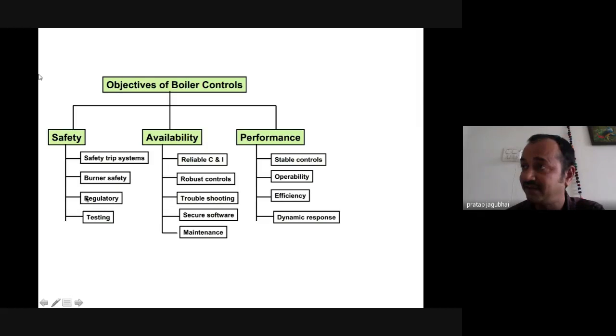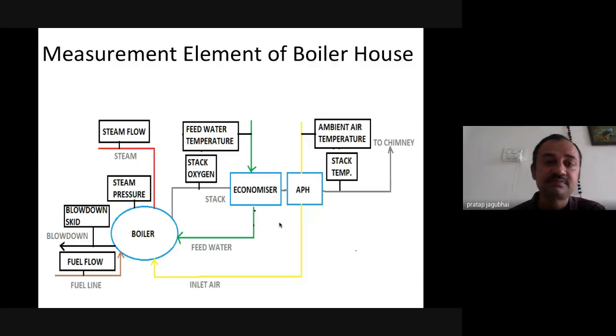The first aspect is safety, with combustion control and regulatory control properly tested. Then the measurement: reliable instrumentation should be placed for proper, robust controls, so that maintenance and troubleshooting can be easily done. And then we should focus on the performance side, so that we have efficient and stable control which can take care of the dynamic behavior of the boiler parameters.